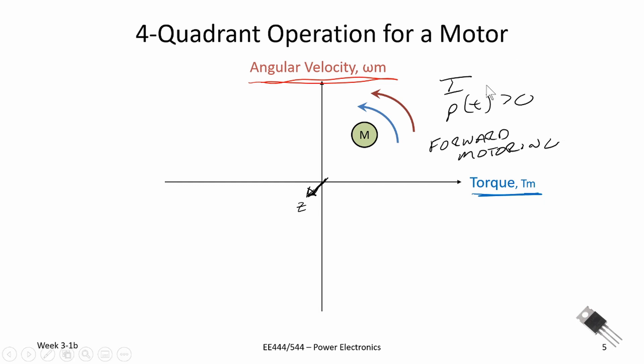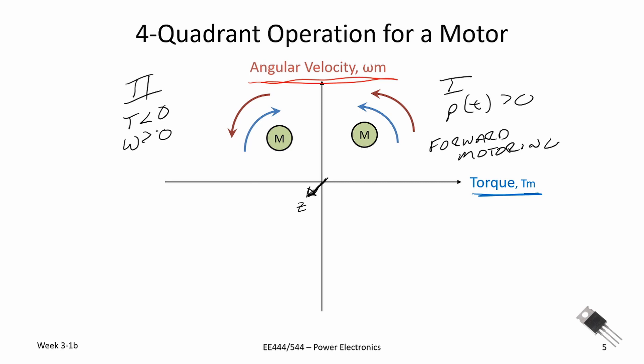Now let's go over to quadrant two. In quadrant two our torque is less than zero — it's reversed — however our angular velocity is greater than zero. The product of those two is going to be less than zero, so the motor is providing electrical energy back. Oftentimes if we can't do regenerative braking, we have to absorb this energy in the form of heat through a resistance of some type. This quadrant is called forward braking.